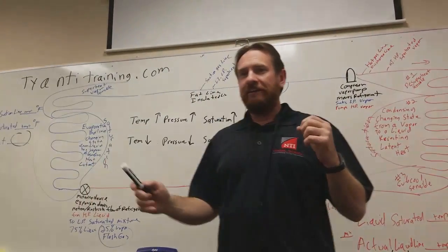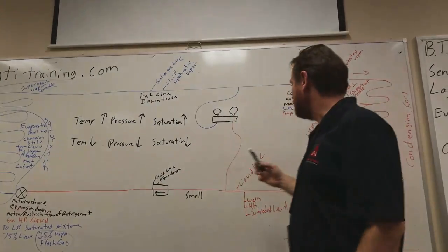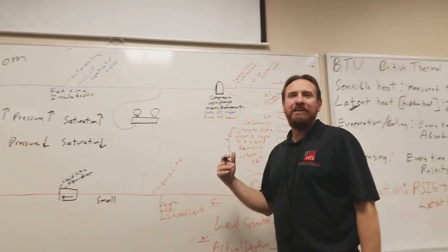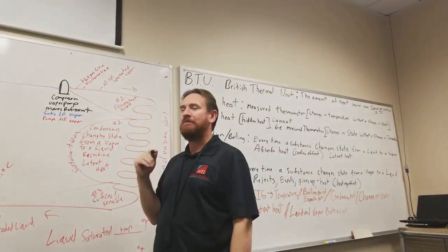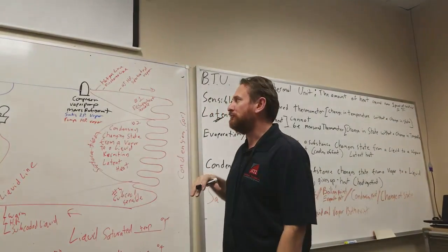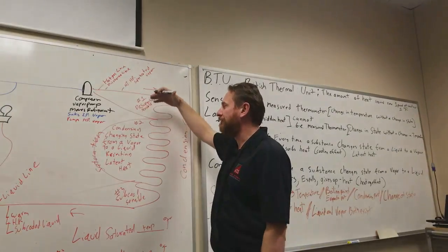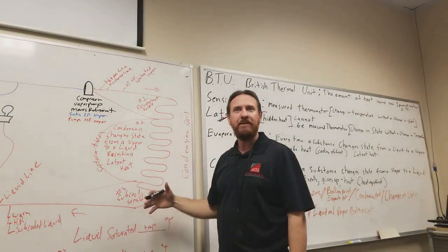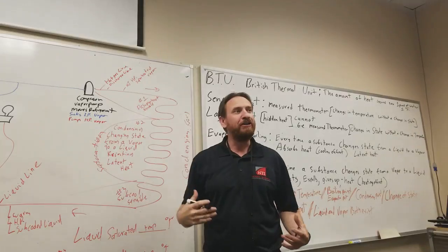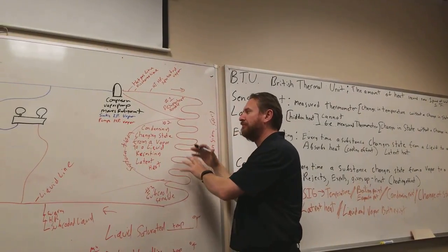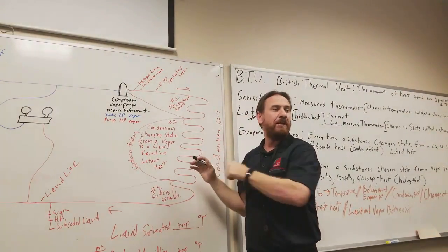Now, we always come into this. I will get there, I promise. People always say, well, what if you overcharge it with refrigerant? Before we answer it, let's think about what an overcharge would be. Overcharge means I'm putting more molecules of refrigerant into this system, right? If I add more molecules of air into your tire, what's your tire pressure going to do? Okay. So if I add more molecules of refrigerant into the system, what's the pressure on this side going to do? It's going to go up.